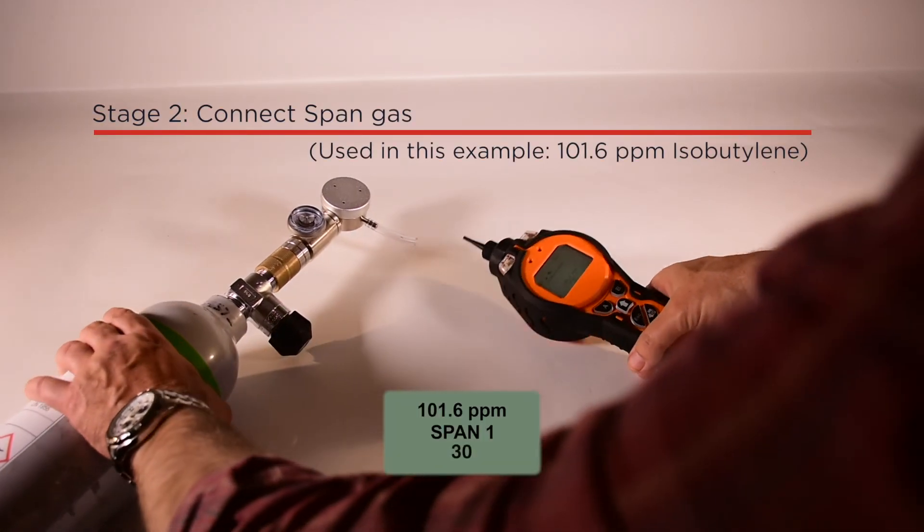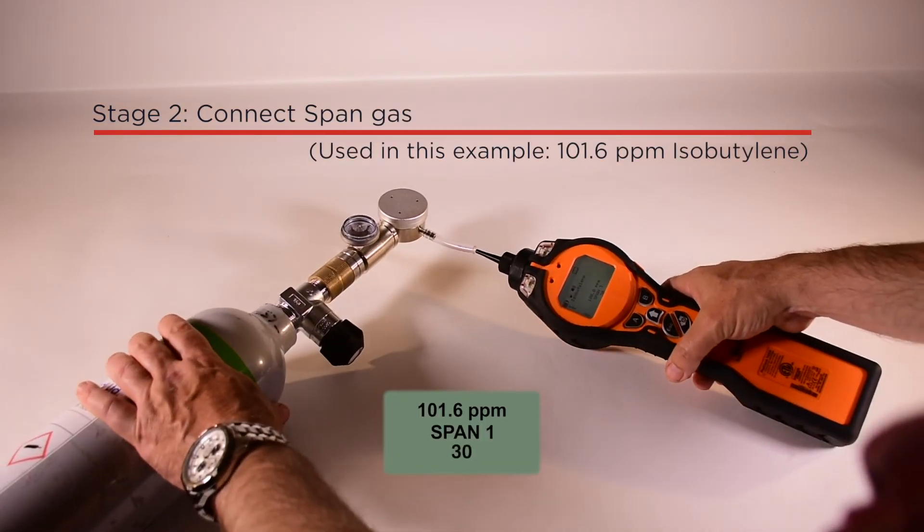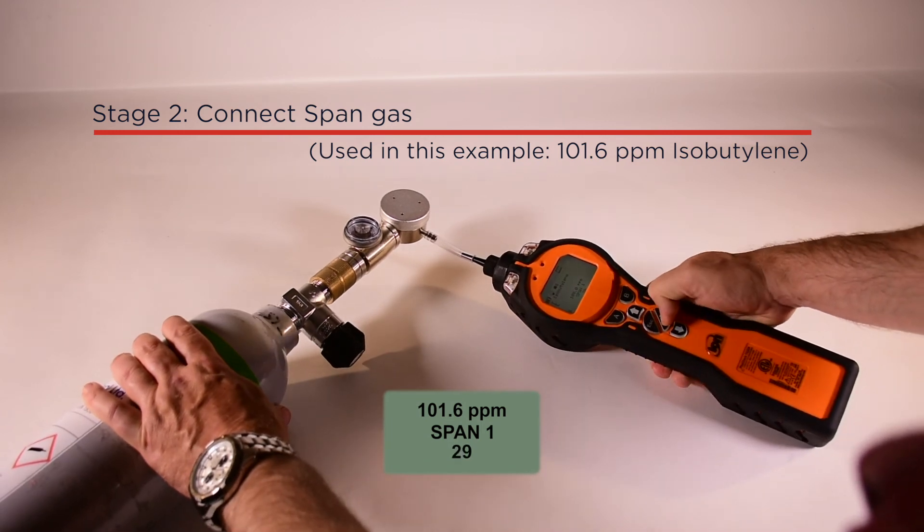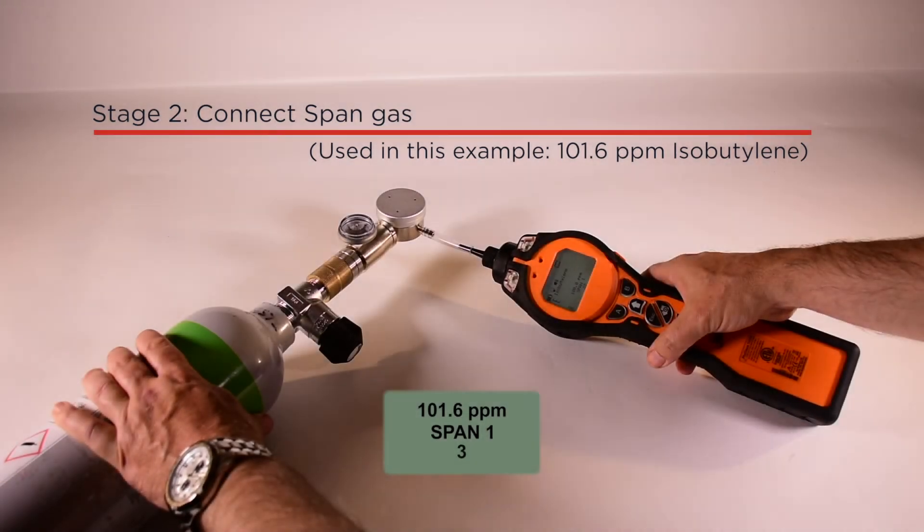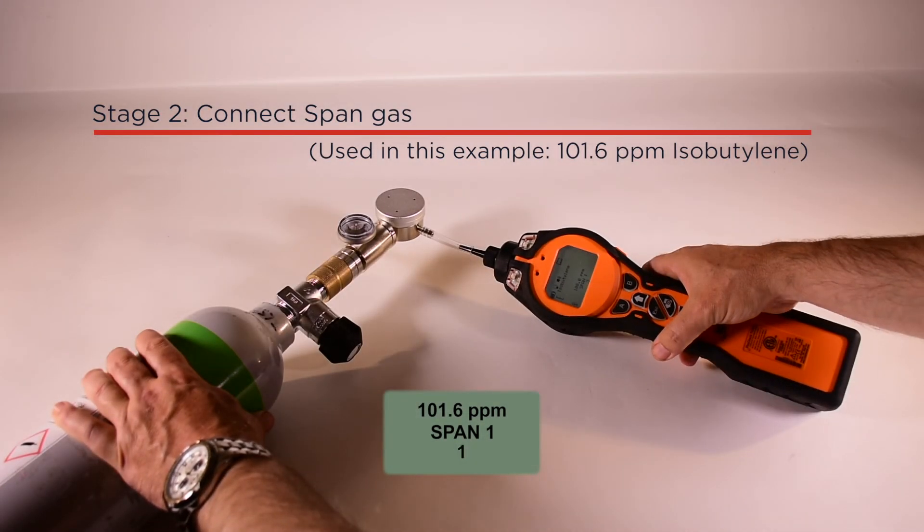The span 1 screen will appear. Connect your TIGER to the gas bottle and press enter. A 30-second timer will count down and then a check mark appears to indicate the span stage is complete. Now press enter.